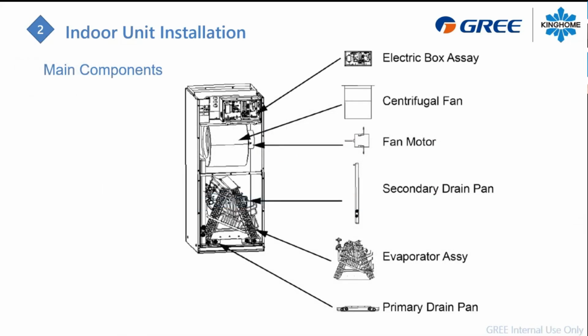So what's inside of it? When you open the panel, you will find an electrical box. So the board is right here inside of it. You will get here your centrifugal fan, your fan motor. It's a DC 3-phase fan motor. You will have the coil assembly right here and a secondary drain pan. So this unit can be installed vertically or horizontally, and you have your primary drain pan as well.